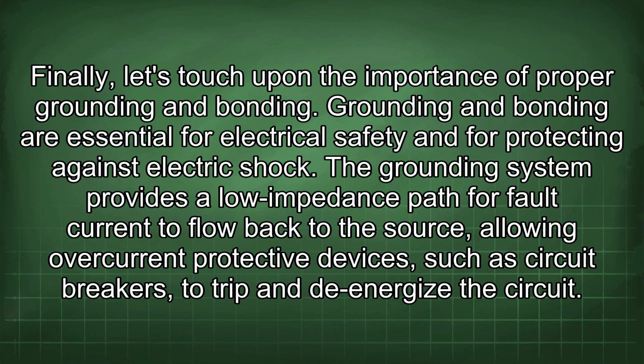Grounding and bonding are essential for electrical safety and for protecting against electric shock. The grounding system provides a low impedance path for fault current to flow back to the source, allowing overcurrent protective devices such as circuit breakers to trip and de-energize the circuit.